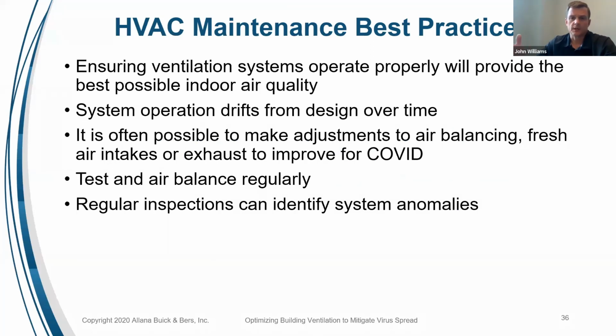I've been literally in hundreds of buildings over the past however many years I've been doing this. And the one thing I can say they all have in common is that they rarely are operating as they were originally designed. Over time, these system components become worn. The systems drift from the original design, which is why it's important that we're inspecting them and we're making adjustments for the outside air ventilation and making sure that everything is operating as it was intended to. So regular inspections, test and balance will always help ensure your system is running optimally.